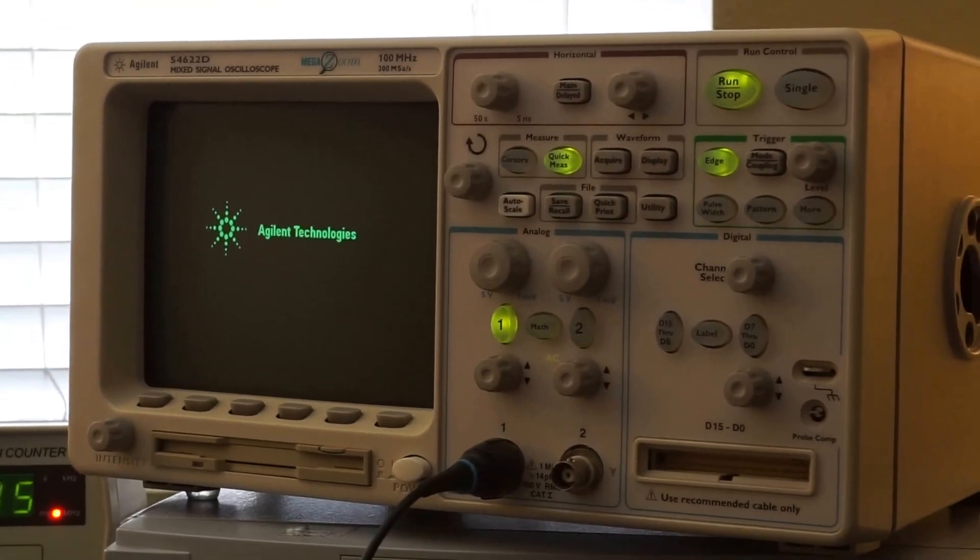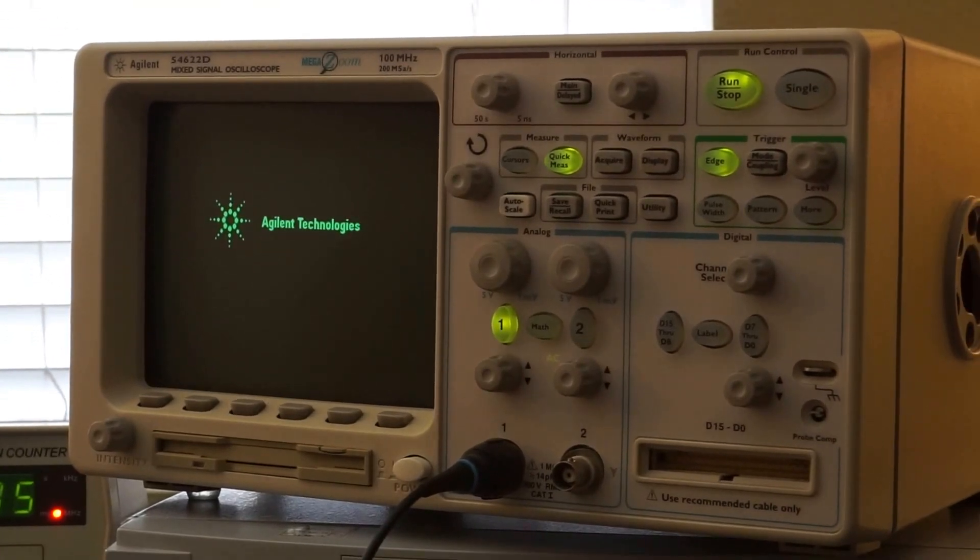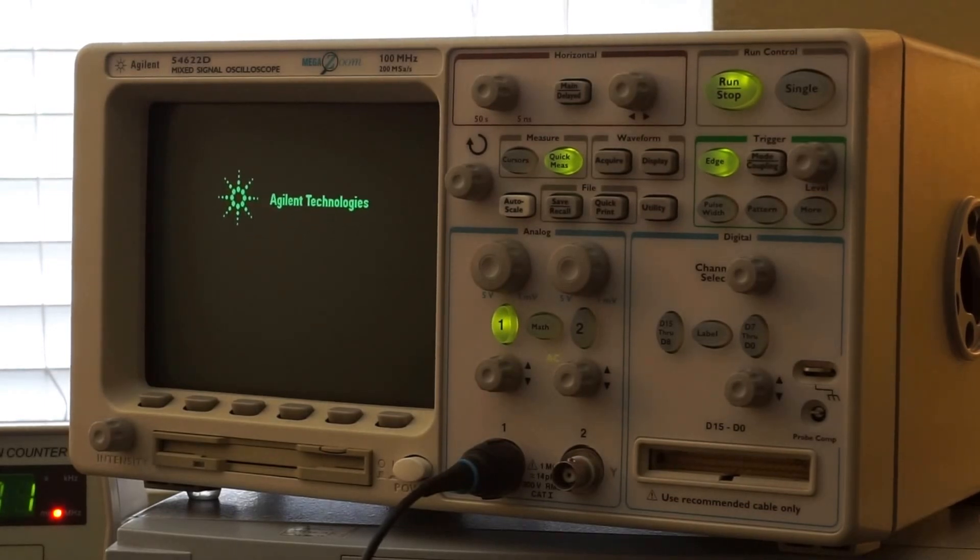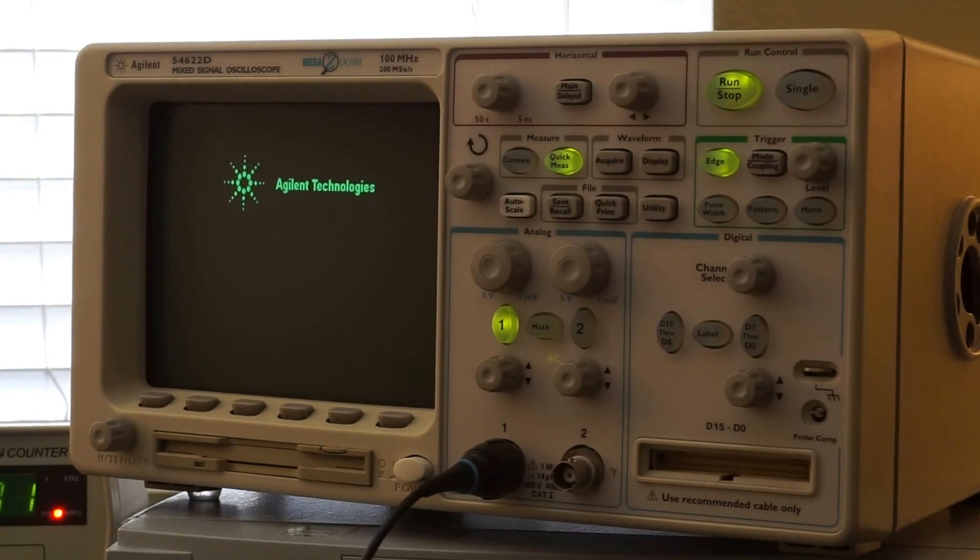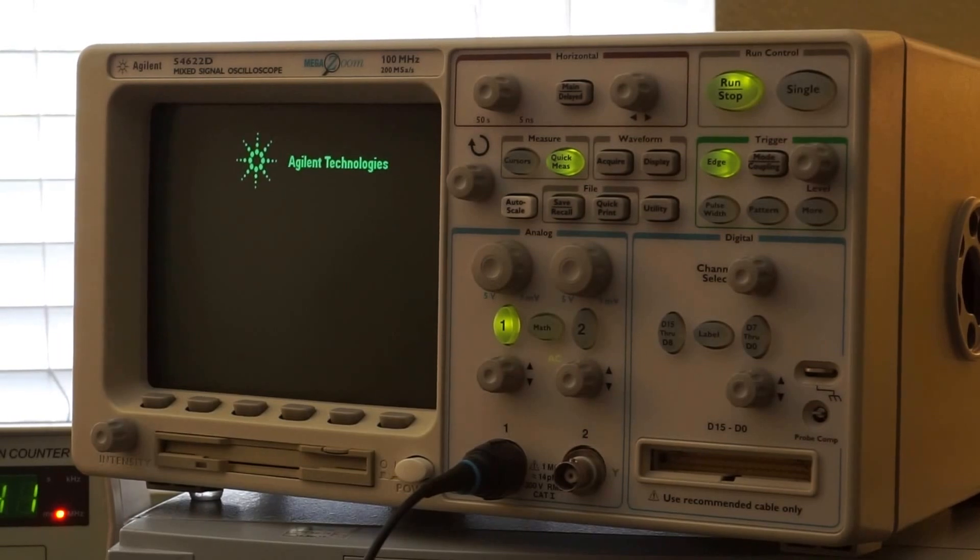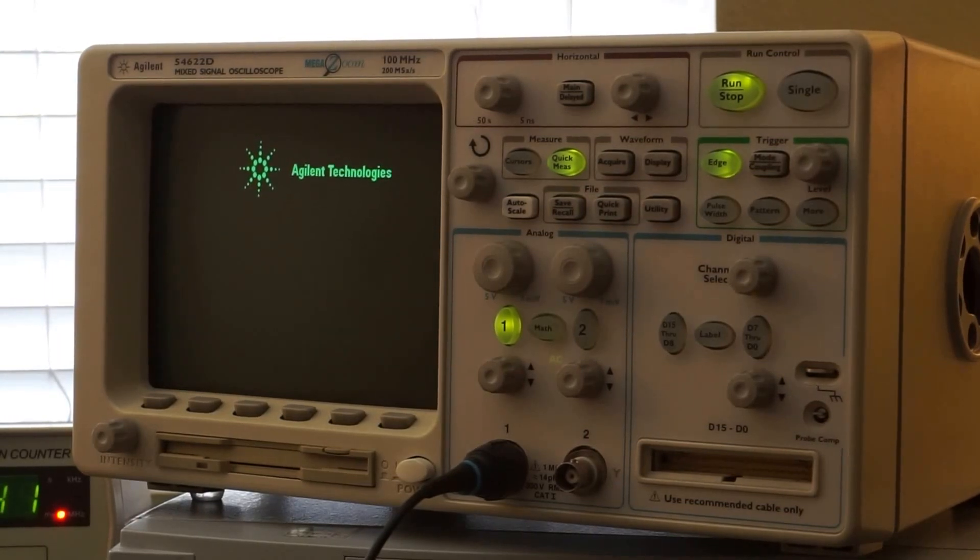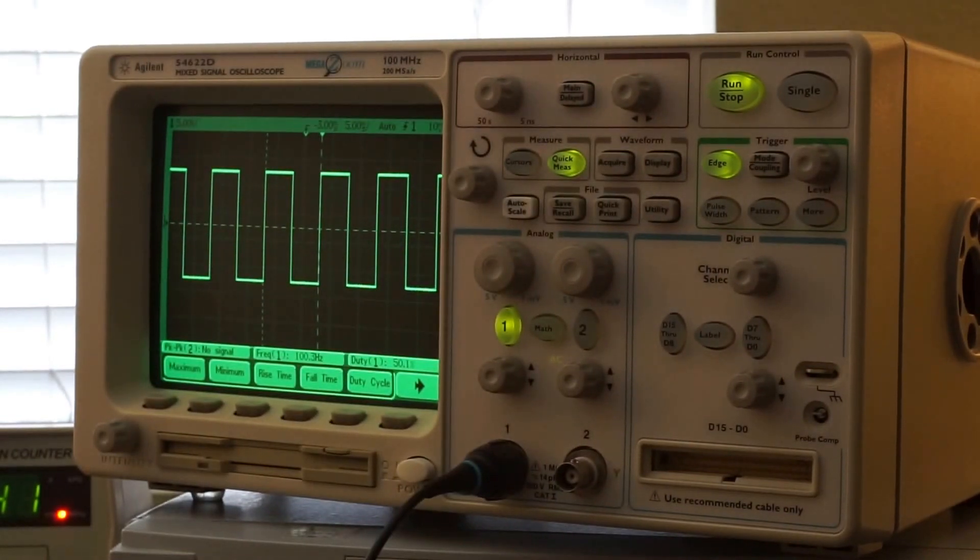So one of the things you do have to remember is that your DMM check plus does have to be in AC mode in order to do the frequency measurements. And I'm now flipping all my oscilloscope probes. And oh yay I'm at the right setting.